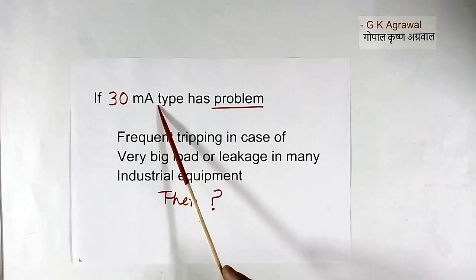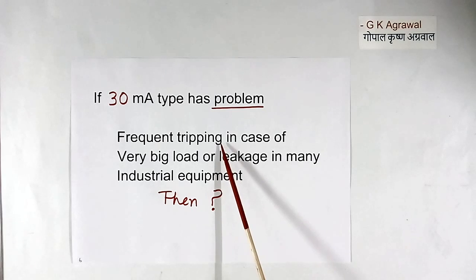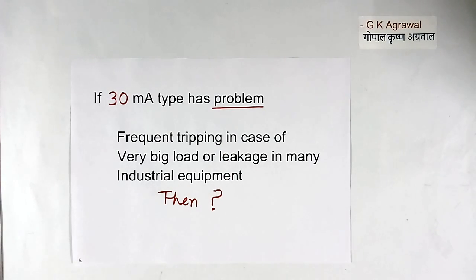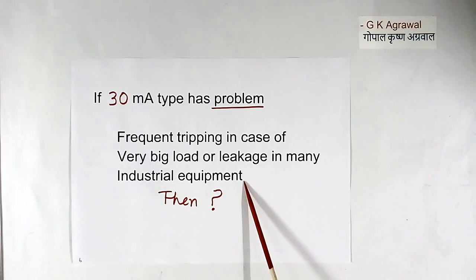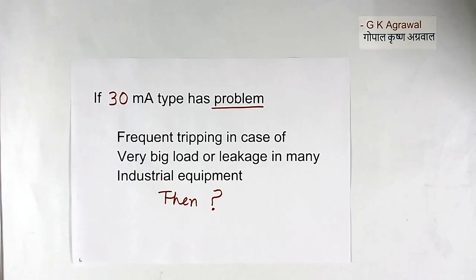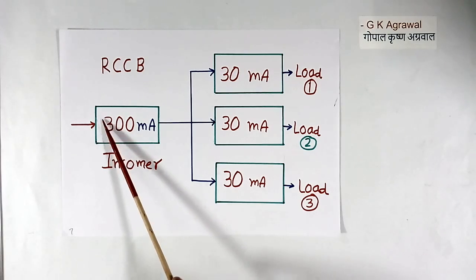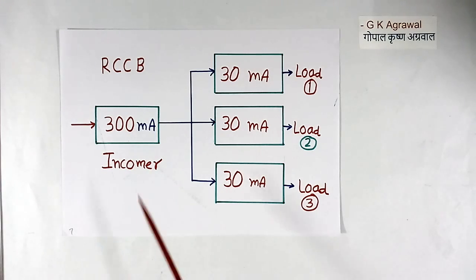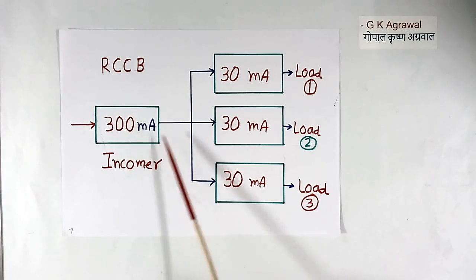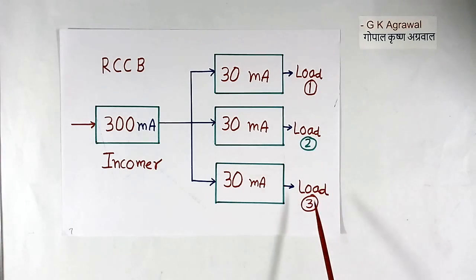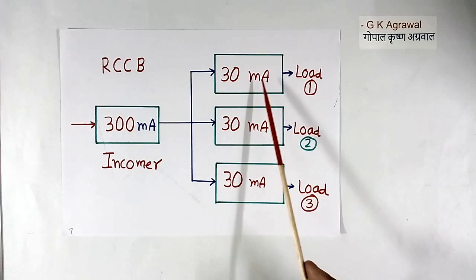Now suppose a 30 mA type RCCB has a problem of frequent tripping. We are not touching any electrical wire, no leakage current is flowing in our body, still it is tripping. This is because of leakage in many industrial equipment, or in the case of very big loads where there may be leakage and it may trip. Then what to do? Then we use a 300 mA type RCCB. But in this case, this RCCB will not give protection to humans — it will not protect us from electrical shock. So what we do is use the 300 mA at the incoming, then divide the loads, and for every small load we provide one 30 mA type RCCB.